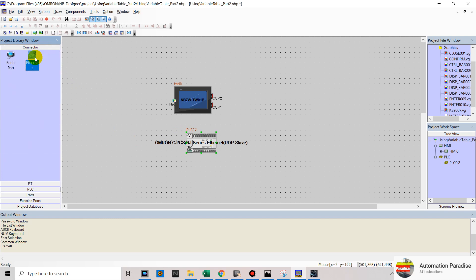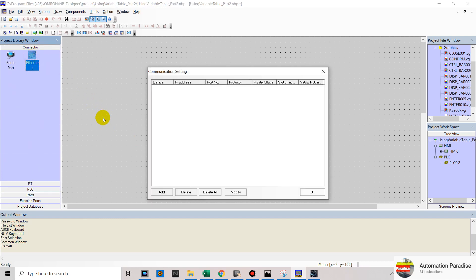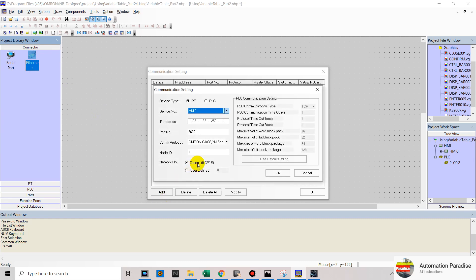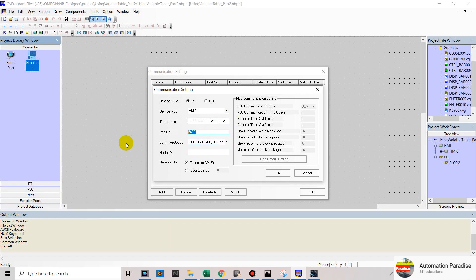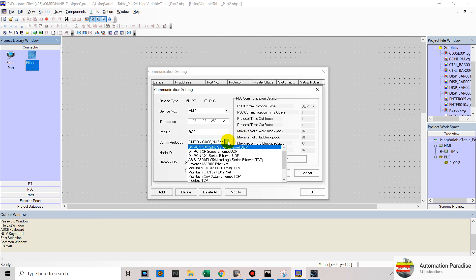Then click Connector and add Ethernet. In your communication setting window, click Add. Then in device type, select PT. Then in IP address, you can use the HMI default, but now we will change to 2. In port number, we will use the default 9600. In communication protocol, we will use the default CJ Series Ethernet UDP.